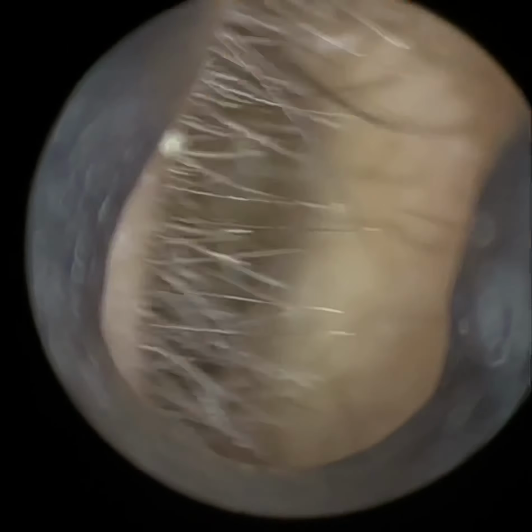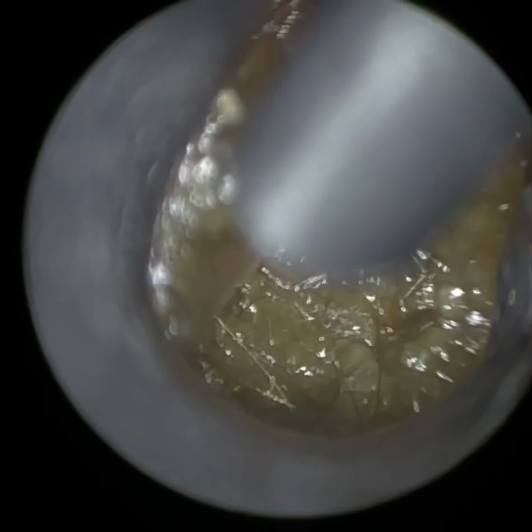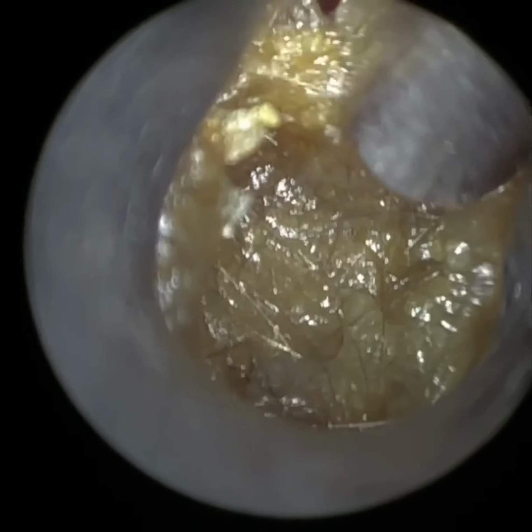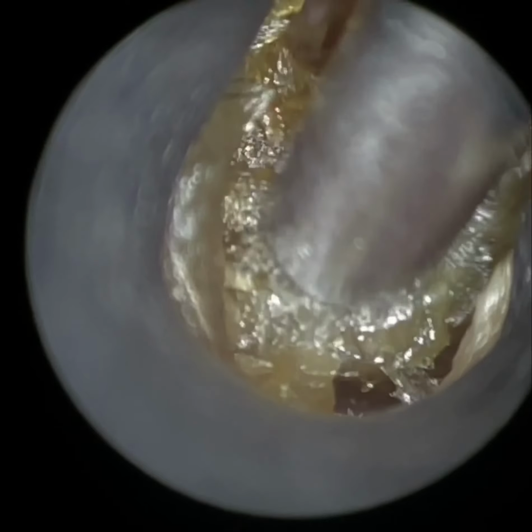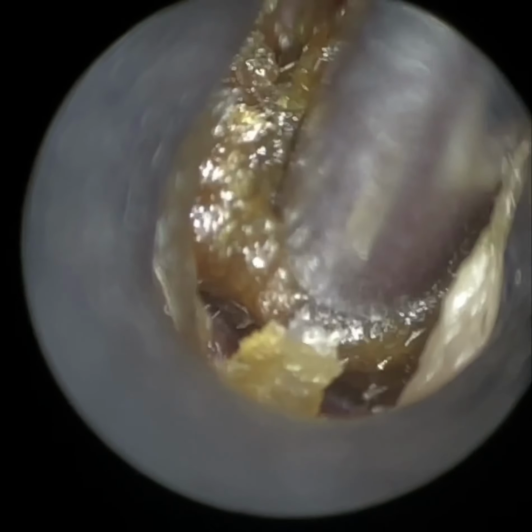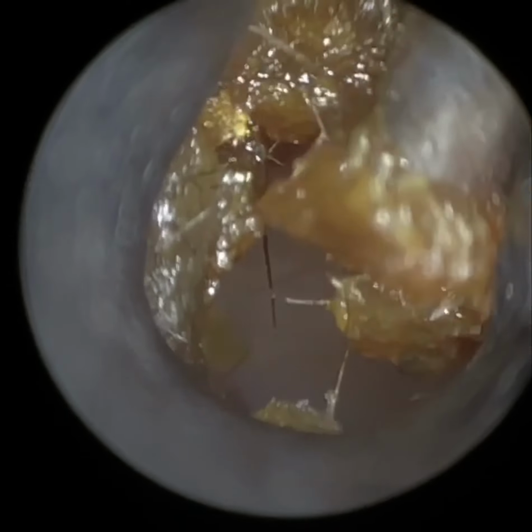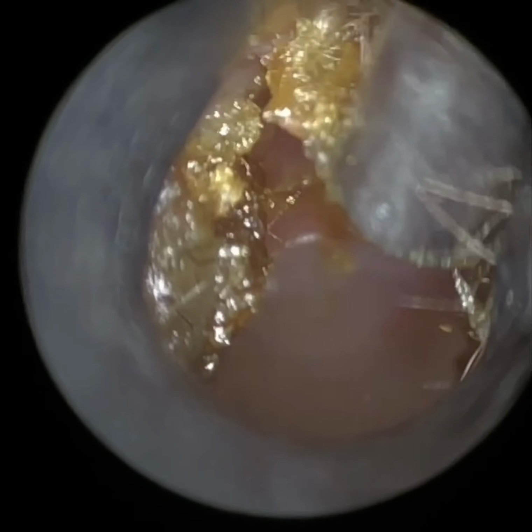We have here another demonstration video of the WAXscope in action, and this is of a patient who attended with medially impacted dead skin, keratin and some wax in the right ear, and they performed the cardinal sin of using a cotton bud, and it's right up against the eardrum. We're just using the 4.25mm specula here just to dilate and widen the ear canal, and you can see we're inserting the Zollner suction probe. Because of the optics we have with the WAXscope, the suction probe is always in focus, it's not in the line of sight, so it's not distorting the visual range of myself when I'm performing this.